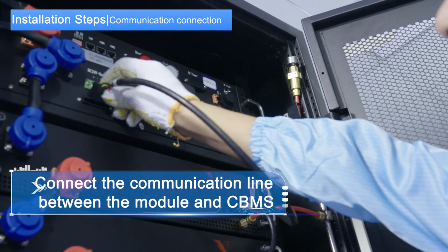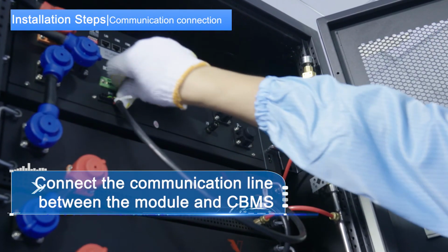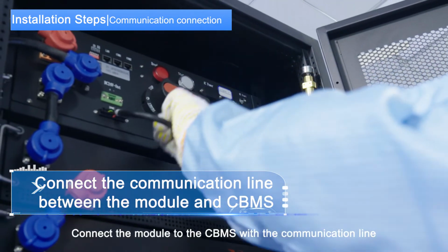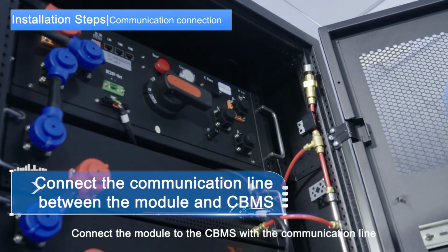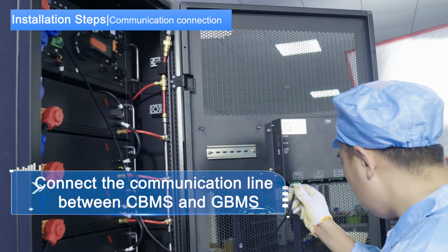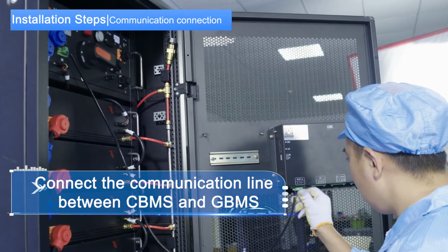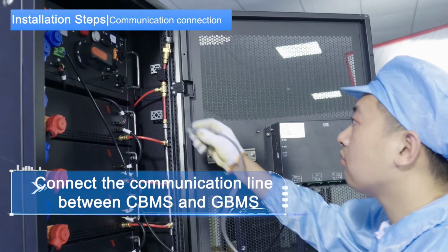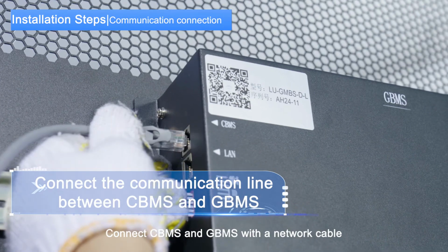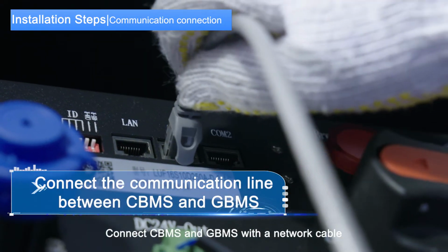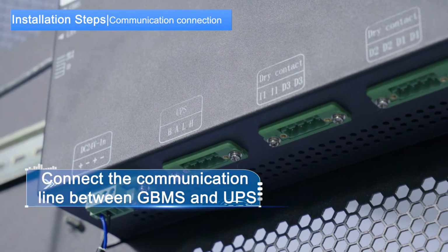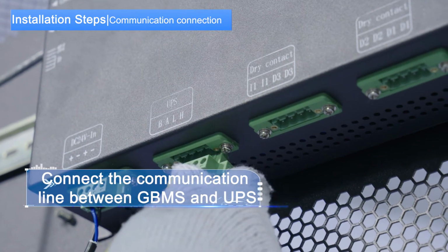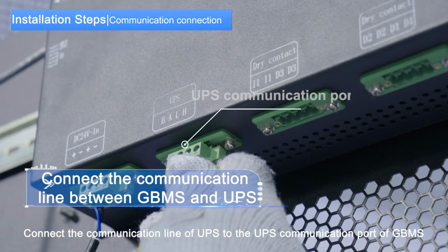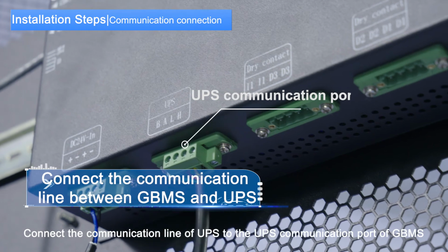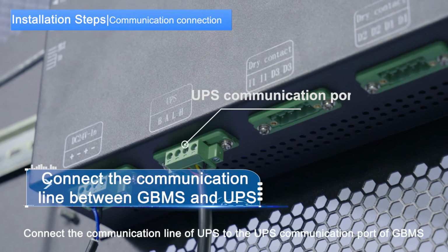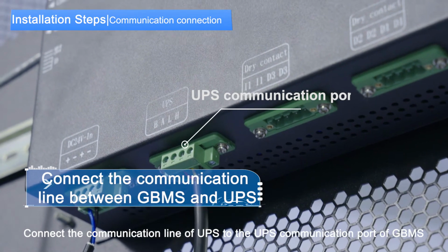2. Connect the communication line between the module and CBMS. Connect the module to the CBMS with the communication line. 3. Connect the communication line between CBMS and GBMS. Connect CBMS and GBMS with the network cable. 4. Connect the communication line between GBMS and UPS. Connect the communication line of UPS to the UPS communication port of GBMS.